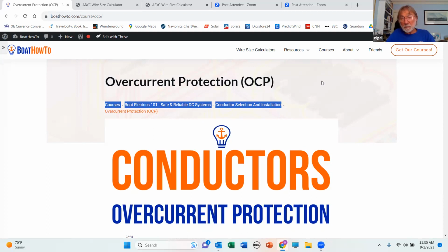If, for example, we've got the engine running because we're using the bow thruster and the windlass, we're leaving an anchorage, and the battery disconnects, and we have no other alternative backup, and we've got a big alternator that we just put on there that cost us a fortune, and it's wired to the lithium-ion battery that has just disconnected, we've just destroyed the alternator. Before the alternator fails, it will have put a massive voltage spike through the boat, and we may have blown every piece of electronic equipment that happens to be turned on at that time, which is all our navigational equipment. We've had instances of this where, in a moment, because of some high inrush current to some device, the batteries have disconnected. There's been no backup in the system. It's a fairly large trawler yacht. You've just blown $100,000 worth of electronics on the boat. So we need that number for lithium-ion batteries. We need the worst case instantaneous load on the battery, and we need to make sure that we cannot exceed it, or if we can, that we have backups in the system.